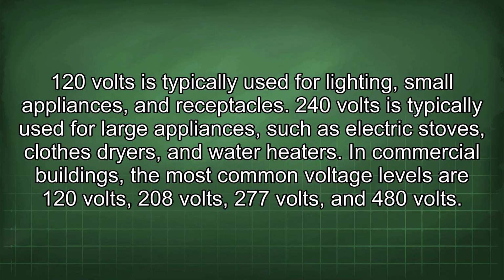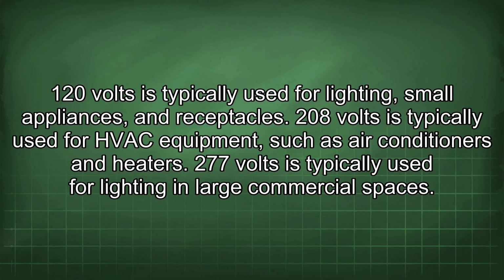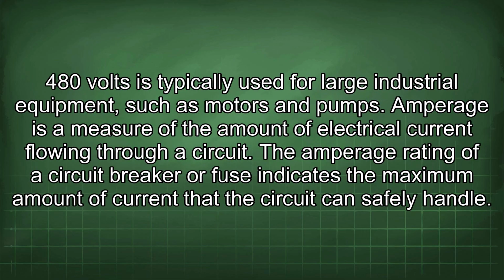In commercial buildings, the most common voltage levels are 120 volts, 208 volts, 277 volts, and 480 volts. 120 volts is typically used for lighting, small appliances, and receptacles. 208 volts is typically used for HVAC equipment such as air conditioners and heaters. 277 volts is typically used for lighting in large commercial spaces. 480 volts is typically used for large industrial equipment such as motors and pumps.